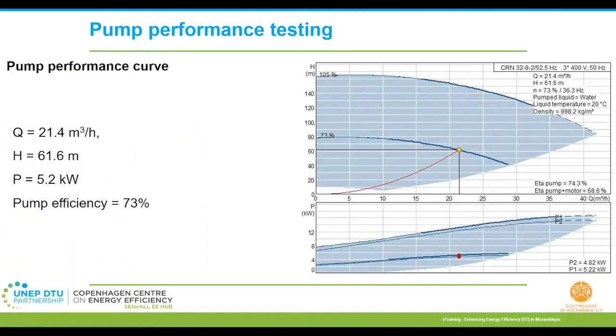So I need your attention here because if you are able to measure the parameters, or you have the parameters in place and evaluate the performances, that is great. But if you do not have these resources, then this is something you can look into. You can ask your pump suppliers, you can actually demand that they give you the pump curve, which they are supposed to give you. So through the pump curves, you can identify approximately what your current level of operations and efficiencies are. I'll just give you an example here.